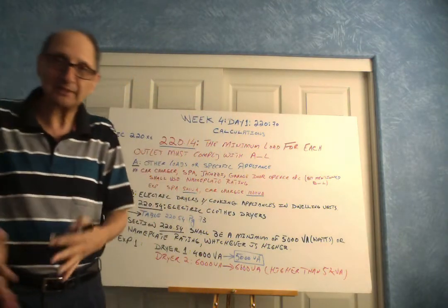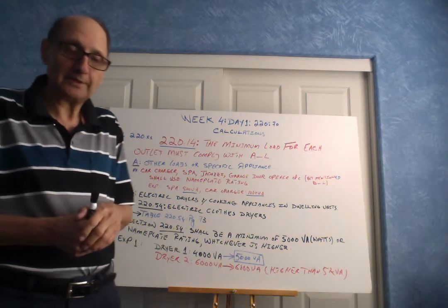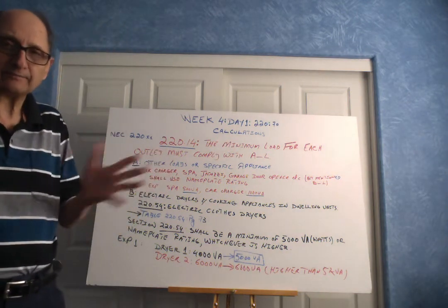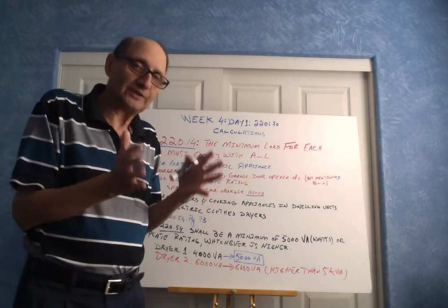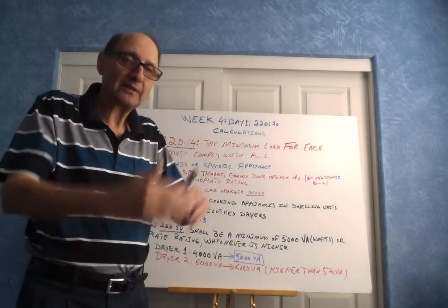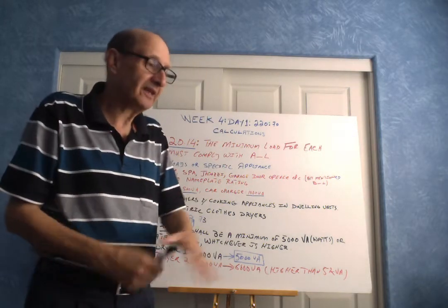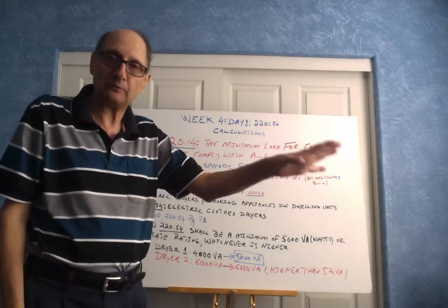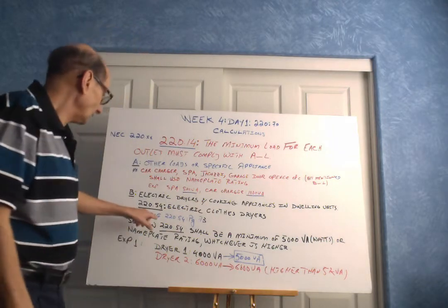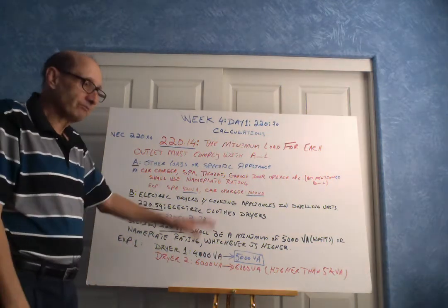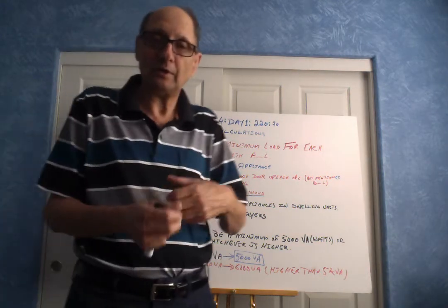There is basically no deduction, no deviation, no derating, nothing at all, 100%. But once we go over 4, then we start derating. That means bringing values down, and that depends on the demand factor that we are going to use. Again, table 220.54, page 73, tells you the demand factors for all of those values.